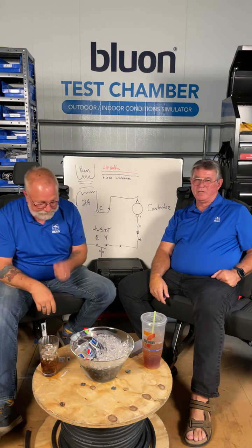How do you bypass the circuit board to get a unit up and running while waiting on a circuit board? You've got to be really, really careful with that, because number one, you need to determine whether or not you're jumping out an operating control or a safety control. And I don't have a problem jumping out safety controls, like people want to jump out high pressure switches. Great, jump out the high pressure switch, but make sure you've got your gauges on there to see what's going on. And you don't jump it out on a permanent basis. Nope. You jump it out just for a moment to see if that's your problem.